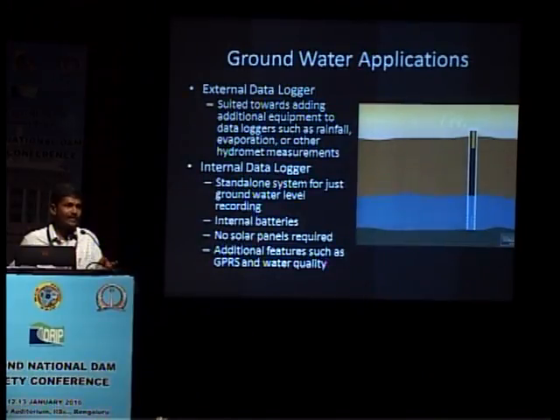So we insist on having a 20 milliamperes current output as a standard output, and that output is connected to a modem, which takes the data to a central server. From the central server, you can talk to the sensor and then recalibrate, program, identify the faults. So it will operate in a protocol. We are trying a modular approach so that a system will come into place - a SCADA system, a graphical user interface, by which you can read, analyze, as well as control the sensor or calibrate the sensor sitting at a remote place, to the extent possible.